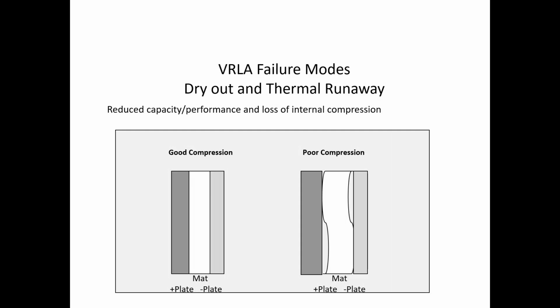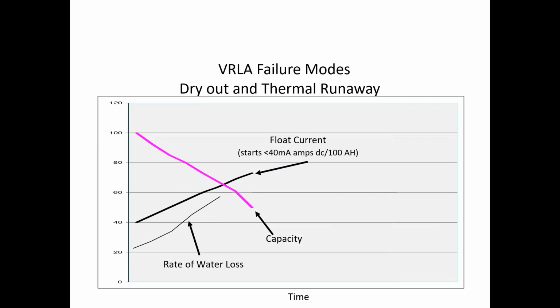This is what I was talking about, just a crude representation of compression. As the battery starts to dry out, imagine you're losing surface and contact area. Say you take a 100 ampere hour battery on the left, and now you've cut in half your surface contact area on the right. You've now gone from a 100 ampere hour battery to a 50 ampere hour battery. So that's where we come to the idea of capacity loss. Again, it's crude, but it gives you an idea. In thermal runaway, as float current increases, the water loss increases and your capacity drops off. You're just exacerbating the dry out of the battery.